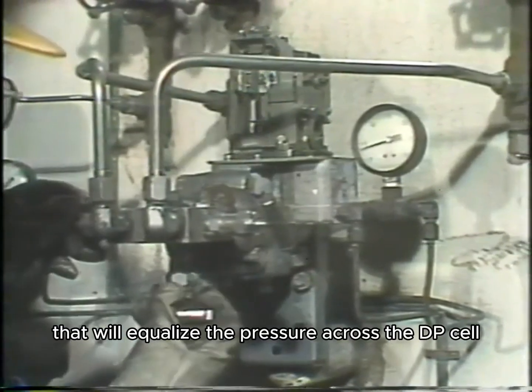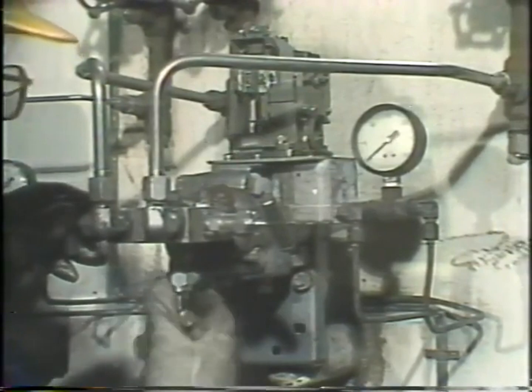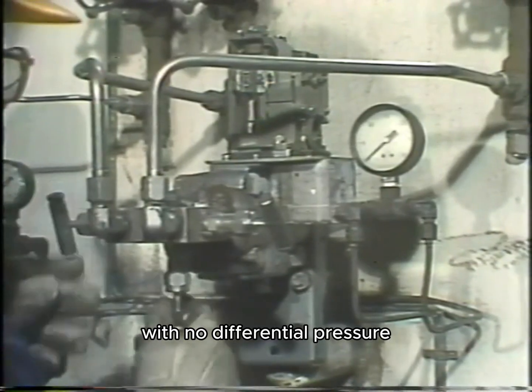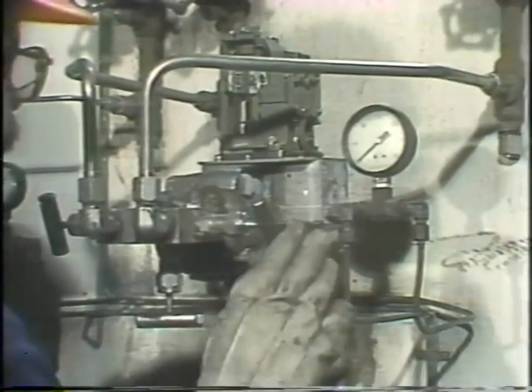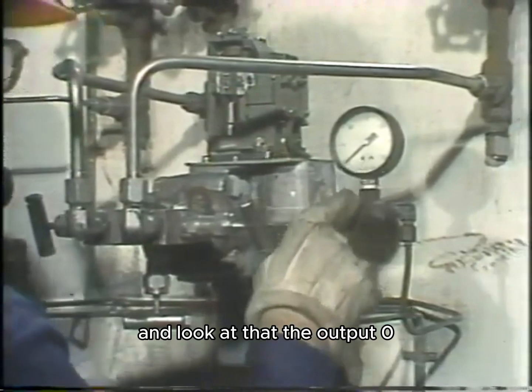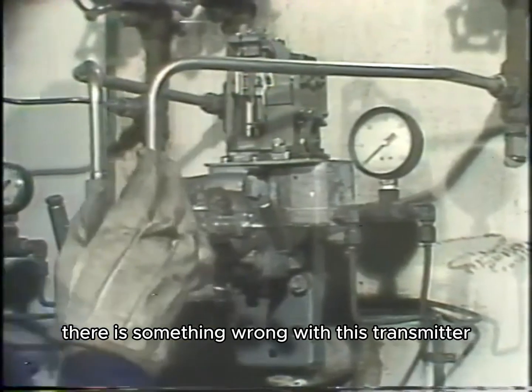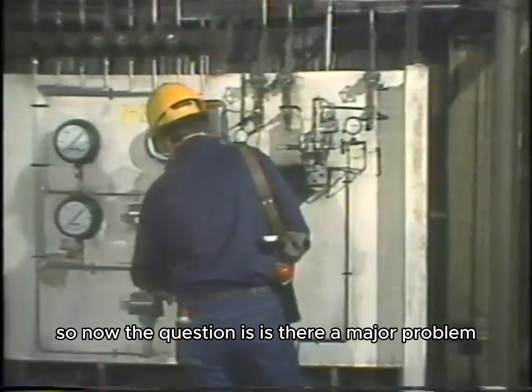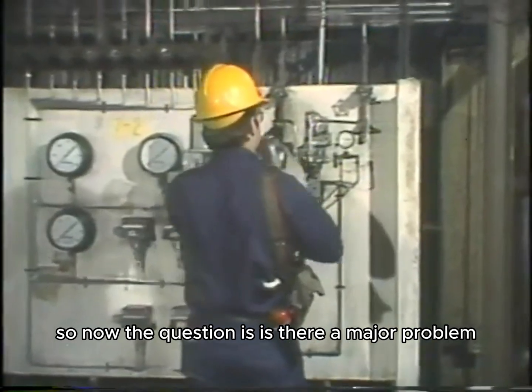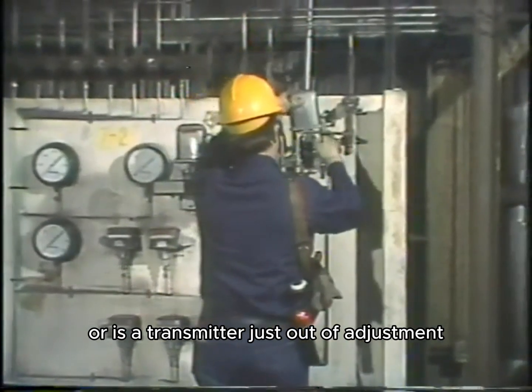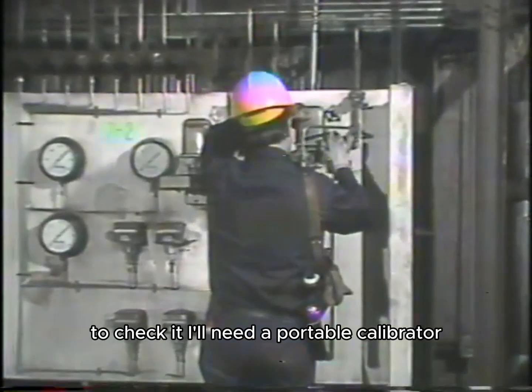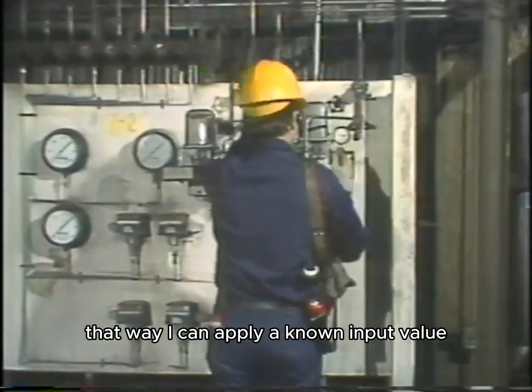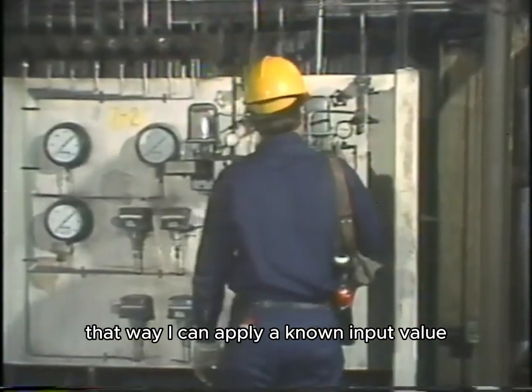That'll equalize the pressure across the DP cell. With no differential pressure, the output should be 3 psi. Look at that, the output's 0. There is something wrong with this transmitter. So now the question is, is there a major problem, or is the transmitter just out of adjustment? To check it, I'll need a portable calibrator. That way, I can apply a known input value and check the transmitter's output.